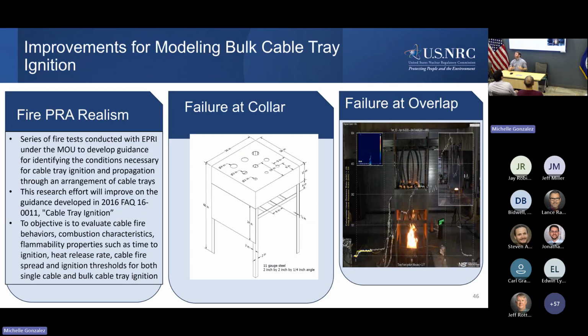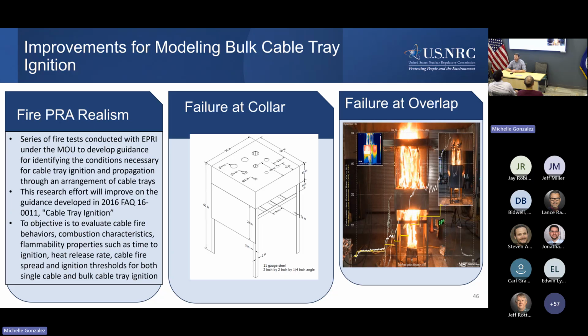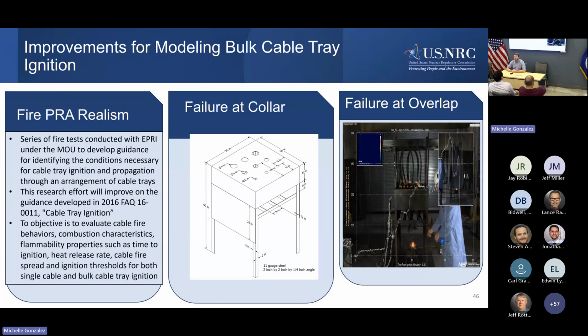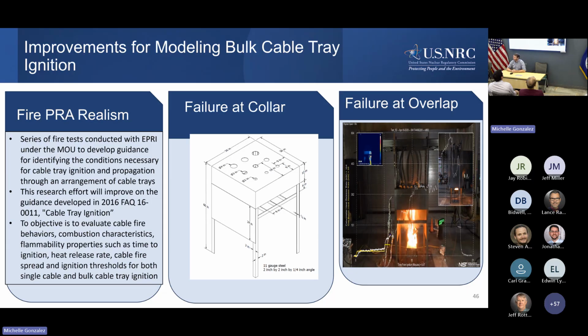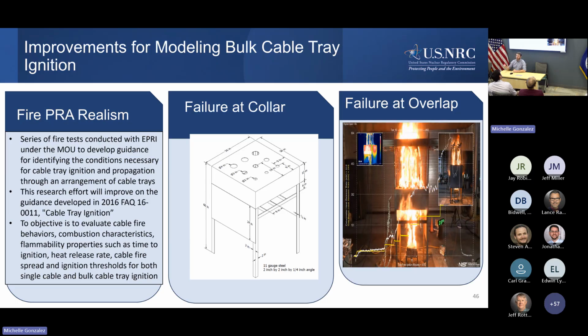One of the more recent projects we're working on with EPRI is improvements for modeling bulk cable tray ignition. There have been multiple methodologies presented for the physical modeling of bulk cable tray ignition, and some important parameters are: at what temperature do these cable trays catch fire when they experience an electrical enclosure or fire underneath them, as well as the timing of how quickly the fire progresses from inside the cabinet to outside the cabinet.